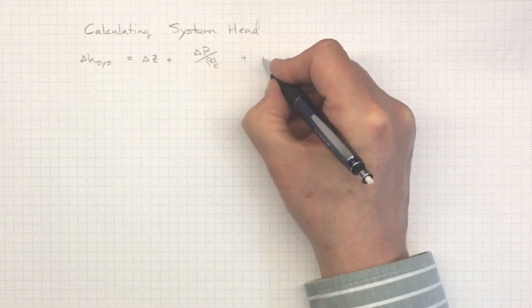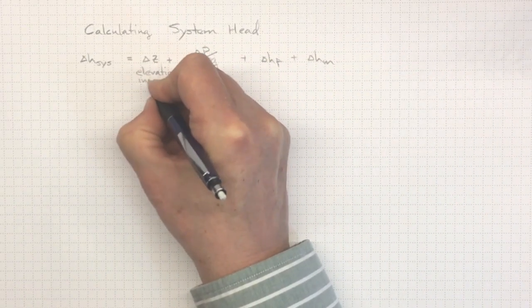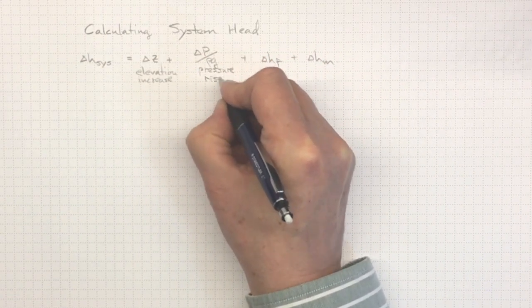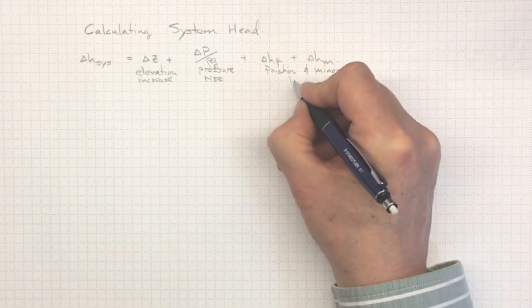We talked about the idea that we'll have a system head, the head rise required across the pump to overcome a change in elevation, a change in pressure, plus whatever dissipative friction losses and minor losses we have in the piping system.